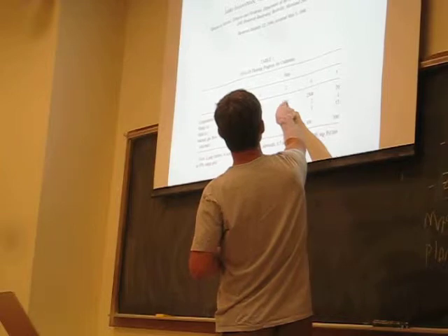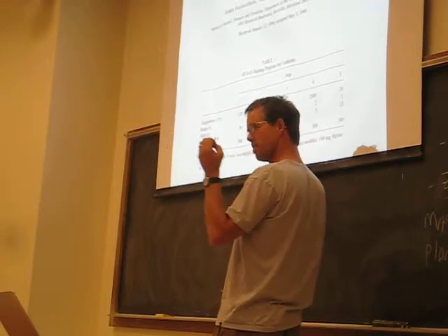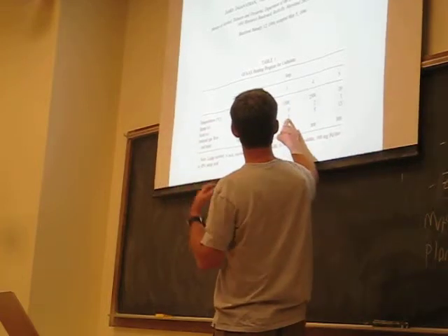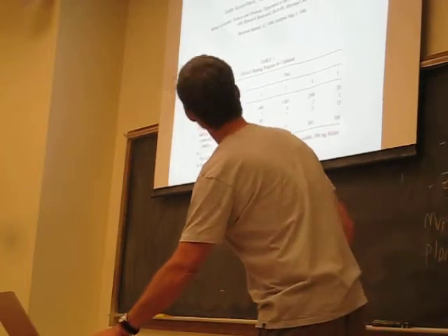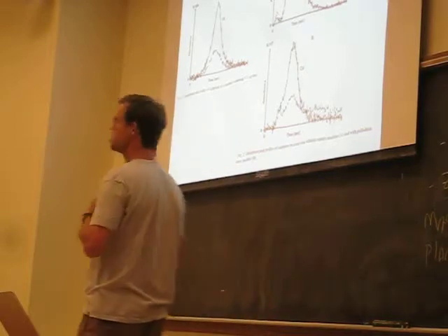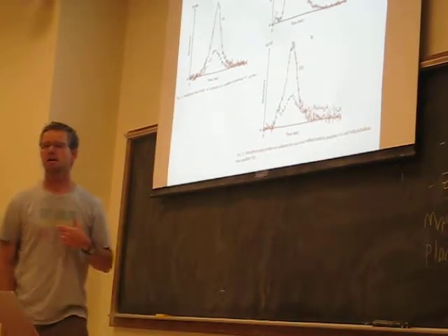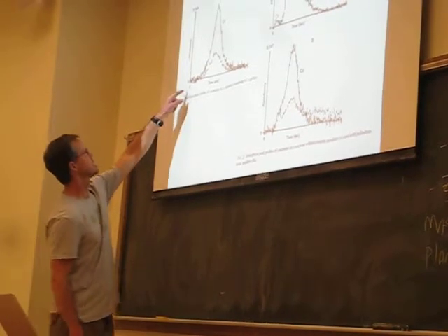And of course, this is the step where they're doing the reading, where they increase the temperature to 1300 degrees and then have no gas, so they have maximum residence time of their volatilized element in the tube gas phase to measure, and they measure for 5 seconds. That's pretty common. So they devised this method, and they show the absorption and background profiles under different conditions. This is a classic example of an absorbance signal.